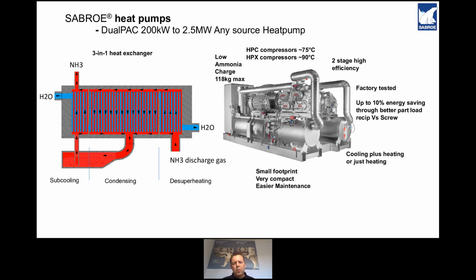And quickly looking at the DualPAC unit here, like I said, the compressors are stacked above the heat exchangers, very low ammonia charge. So this for health and safety reasons, it's a very, very good thing. The 2-stage efficiency, these are fully factory tested. We can invite your customers, yourself, your engineer to the factory, and we will test this unit in front of you at your conditions. So you can see it work before it actually goes onto your system.